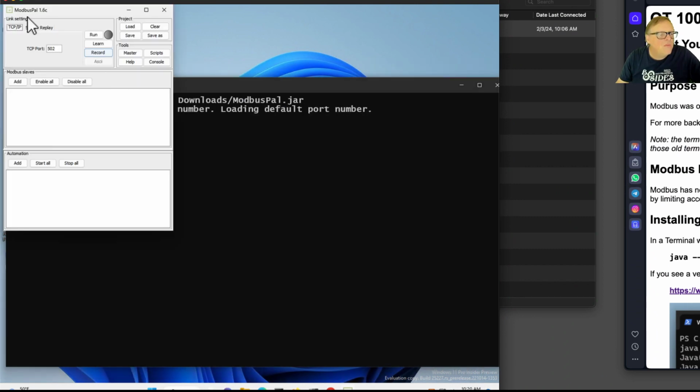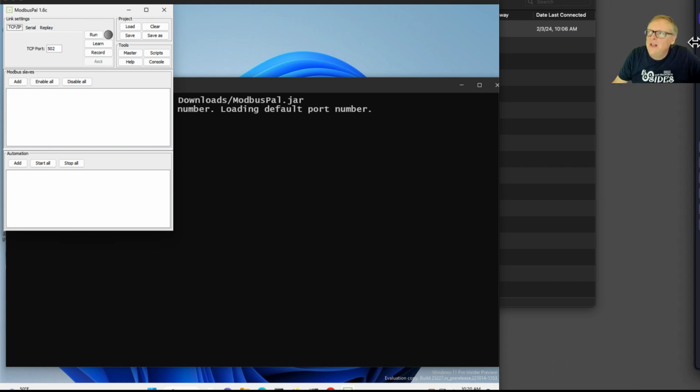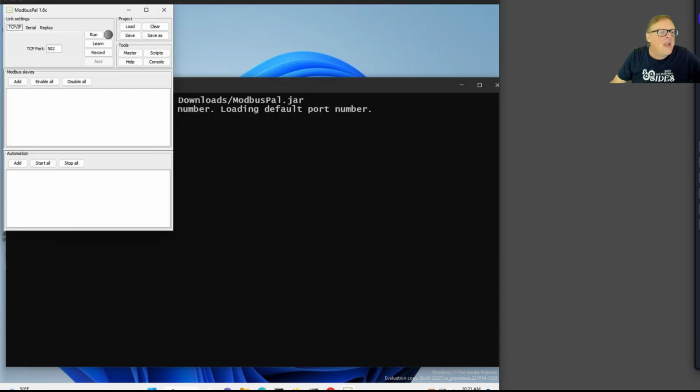This will run an endpoint device, which is called the slave, which is the one connected to the hardware, and it acts as a TCP server listening on a port. That's kind of backwards. It's a TCP server, but it's acting as the endpoint device, which you could call the slave, and it's listening on a default port of 502.